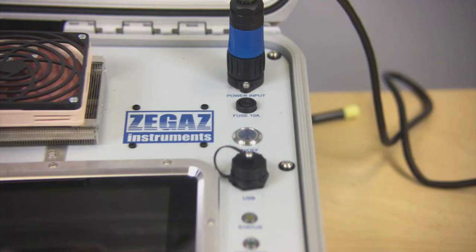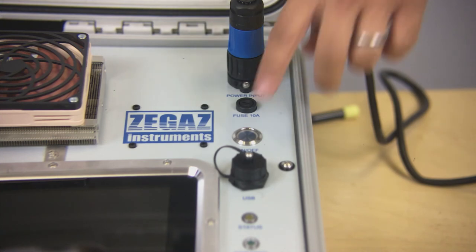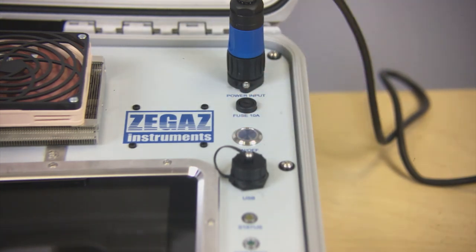If you attempt to power up the unit and the power button does not illuminate, first make sure that you are using the appropriate power connectors and that there is voltage at the source. Next, check the 10-amp fuse located on the instrument panel.